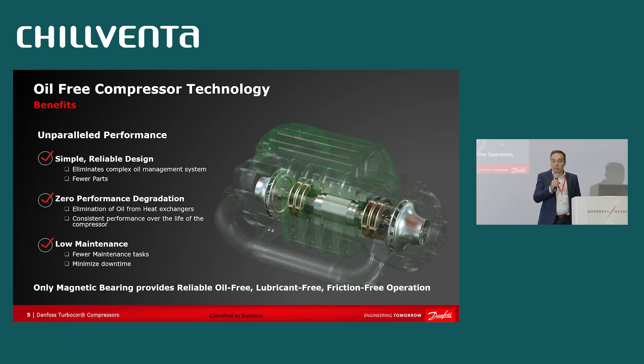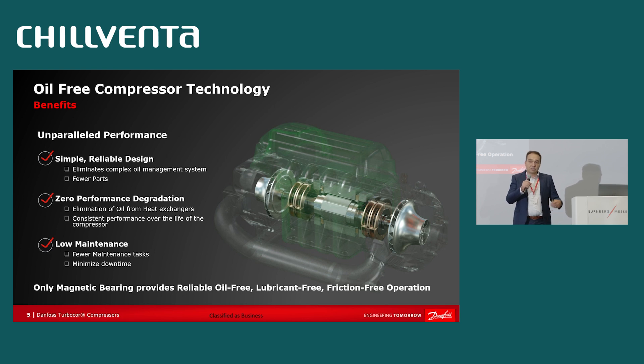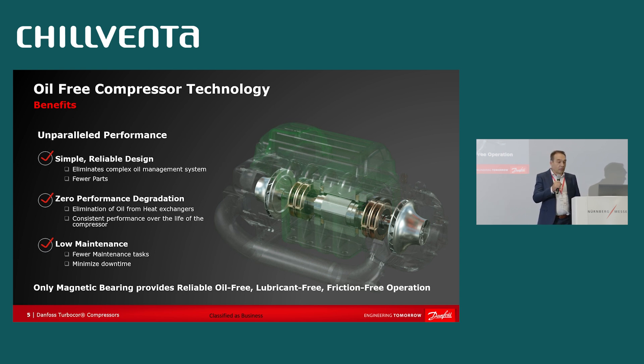Another key benefit is lower maintenance. By having no oil in the system, you can eliminate all of the tasks associated with that. The key differentiator for Turbocor and magnetic bearing is that it is friction-free — no parts in contact. That's not the same for everything that calls itself oil-free. Only magnetic bearing is friction-free and lubricant-free, because a lot of oil-free systems will use refrigerant as the lubricant itself, which has potential failure modes. By eliminating the oil and using mag bearing, you avoid any friction or lubricant.